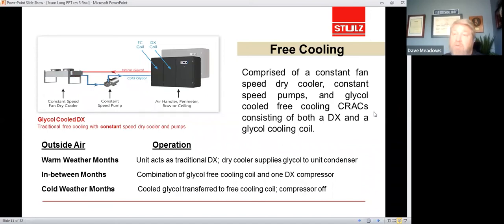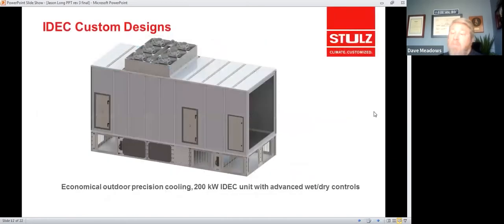And then in the cold weather months, which in certain locations such as Colorado, there's plenty of opportunities and hours per year to operate as a compressor-free glycol-cooled unit, basically think of it as almost a chilled water unit now. So we have the ability to provide 100% of the cooling with very precise control at just a fraction of the energy usage that's typically required to move that heat. Very quickly, I'd like to talk about IDEC designs. This is the indirect evaporative cooling. These are units that are designed specifically for data centers. Once again, we are trying to remove the cooling without the energy cost of running the compressors.